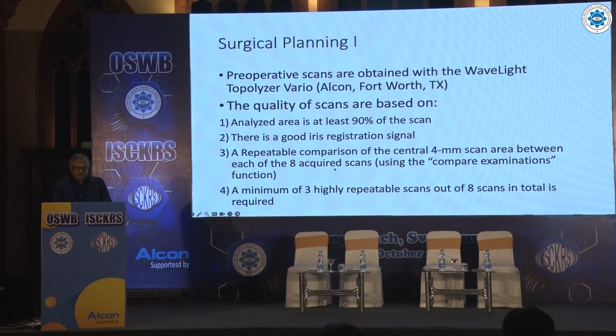Now coming to the surgical planning, preoperative scans are obtained with the help of WaveLight Topolyzer Vario. The quality of scans is judged on whether the analyzed area is at least 90% of the scan, there is a good iris registration signal, and a repeatable comparison of the central 4 mm scan between each of the 8 acquired scans using the compare examination function. A minimum of 3 highly repeatable scans out of 8 scans in total is required.